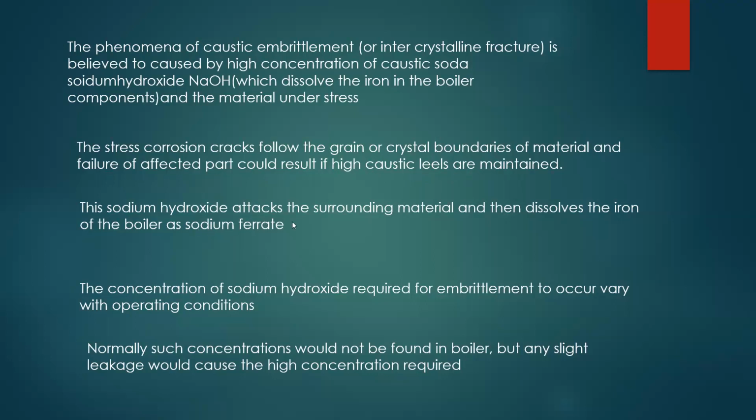This sodium hydroxide attacks the surrounding material, and then dissolves the iron of the boiler as sodium ferrate. The concentration of the sodium hydroxide required for embrittlement to occur varies with the operating condition of the boiler. Normally, such concentration would not be found in the boiler, but any slight leakage would cause the high concentration required.